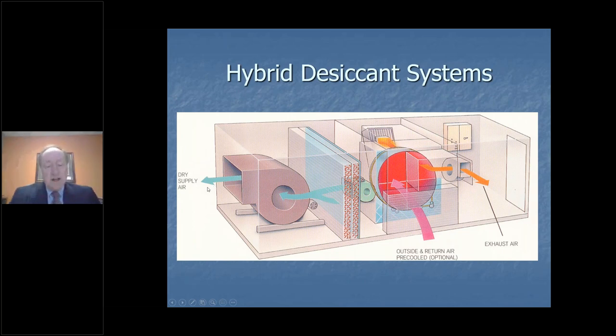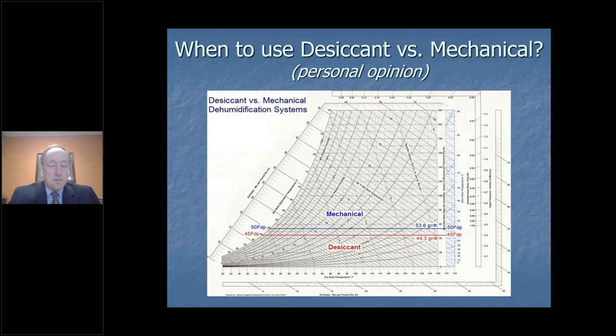People ask me oftentimes, Mark, when should I use a mechanical system? When should I use a desiccant system? My particular rule of thumb would be if I'm trying to achieve above a 50 degree dew point, I can very easily do that with a mechanical system, and I would tend to use mechanical systems above that. If I knew that we needed to absolutely maintain a 45 degree dew point and lower, then I would likely go with the desiccant-based product for that.